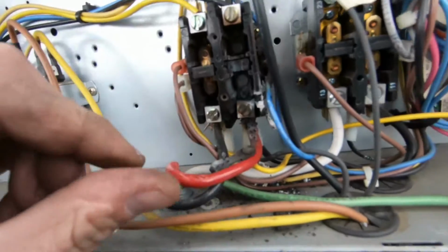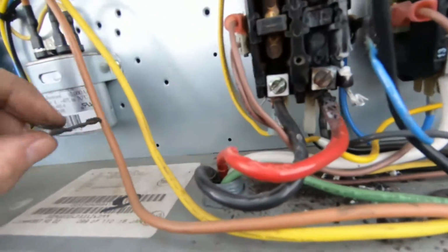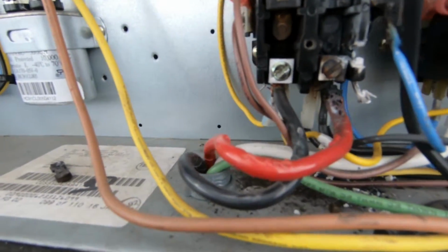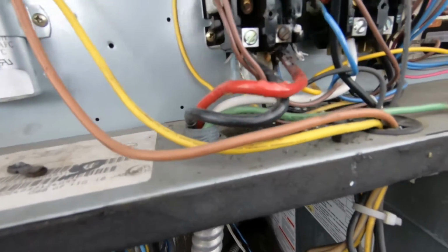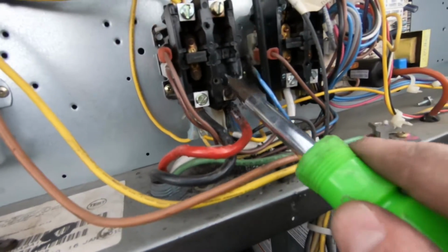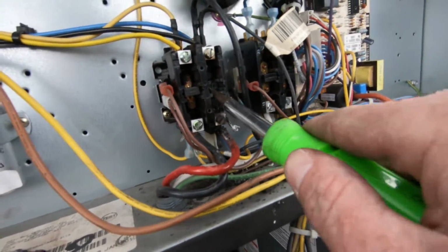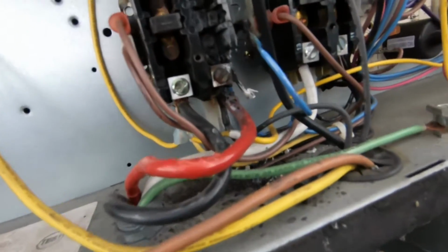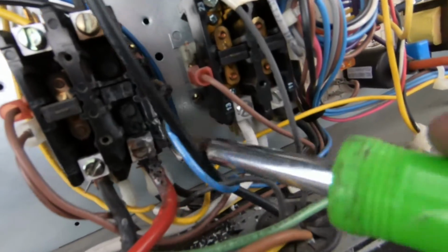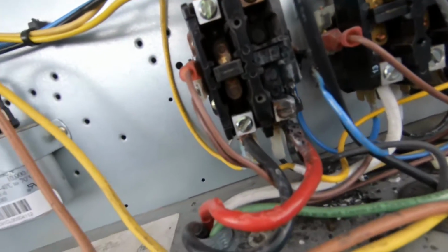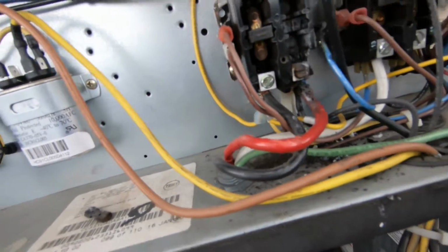Look at that, guys. Totally melted wires. This contactor's completely toast. I mean, it's just busted apart. We're not to do any repairs on site. Everything has to be quoted, but you can see this whole thing is just melted. I'm gonna test that compressor. I can't really run it, but you can see there, that's completely melted and broke apart.